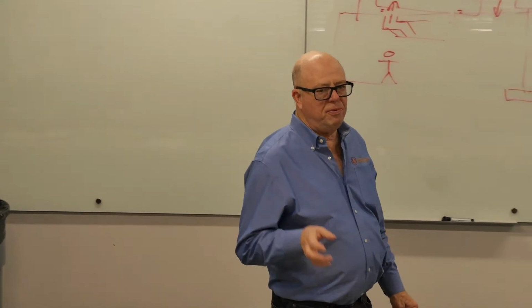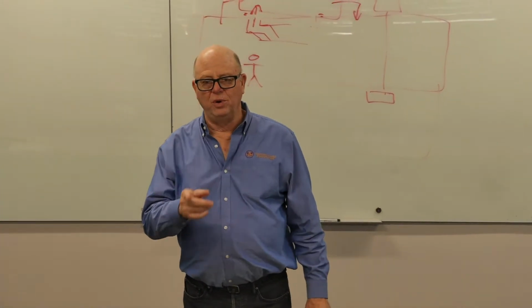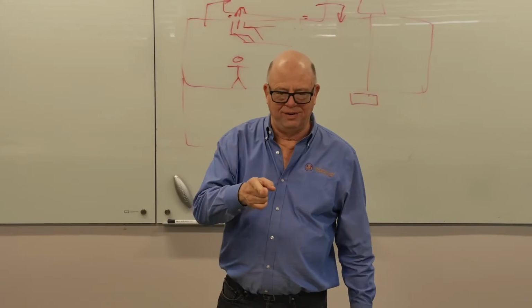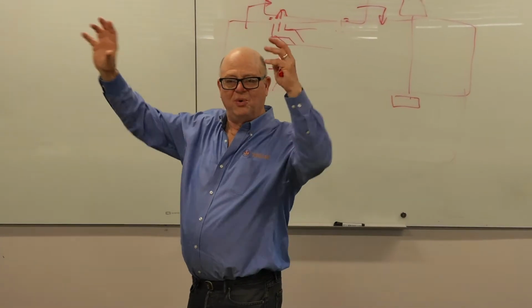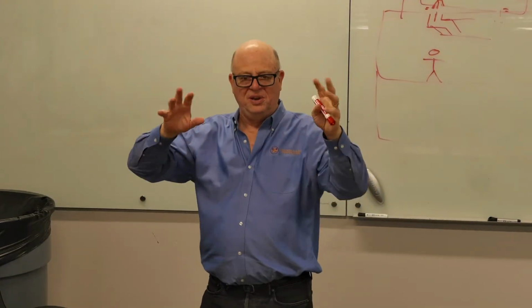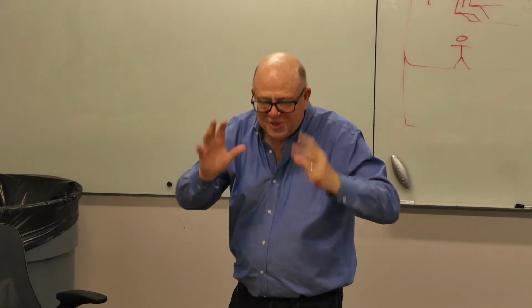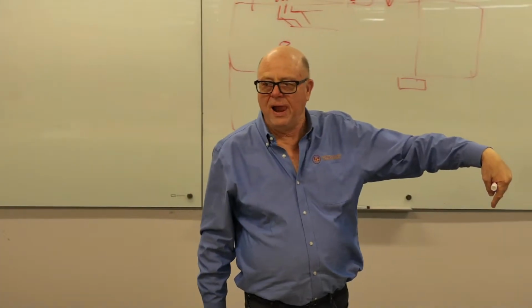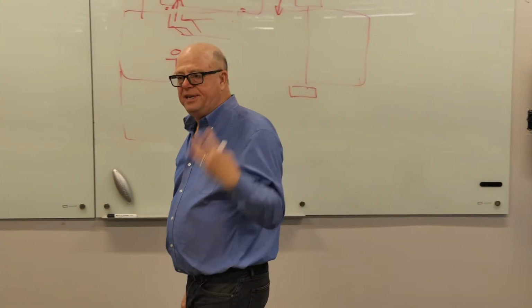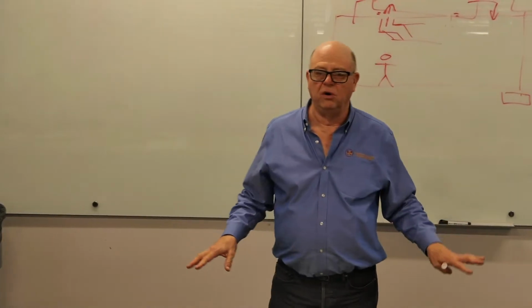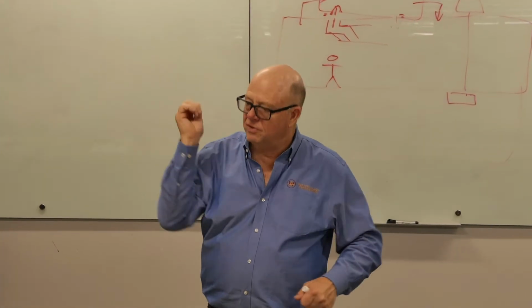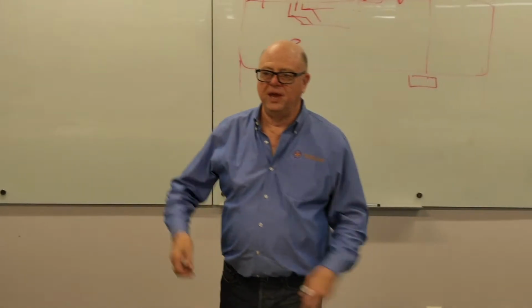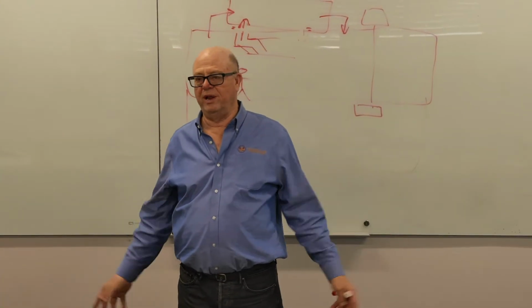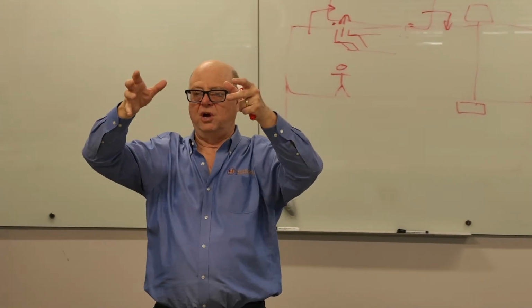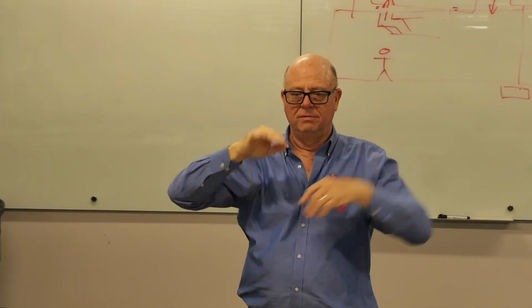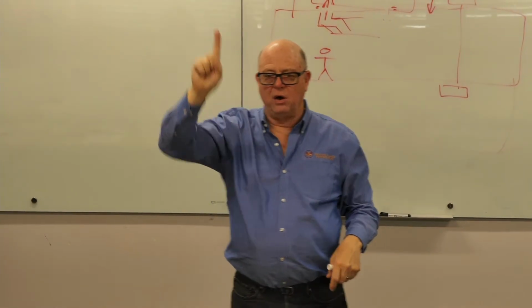What if you want to do something a little more? We put a sound boot in at Fox Studios inside the recording studio where the people sit and get interviewed and the news people get up there and the camera's on them. Well, over in the corner is their server room. And like every IT group on the face of the earth, they kept putting more and more servers into the racks. That meant they had to have more and more supply air. We finally ran out of available supply air, so then we had to put an exhaust fan in the room, with spring flex, to blow it out.